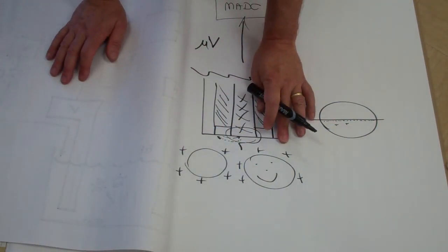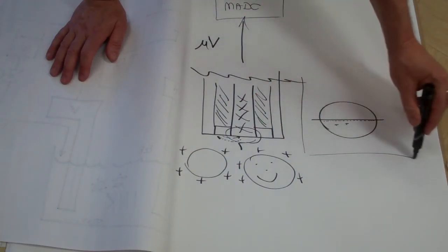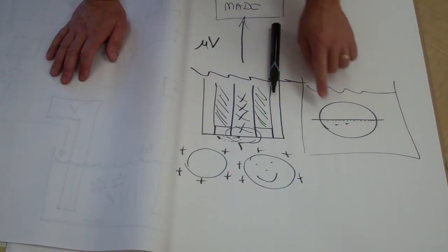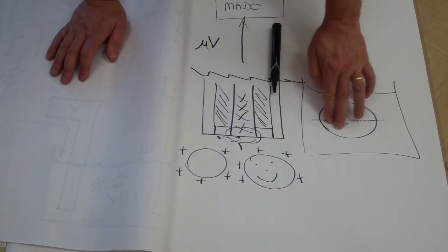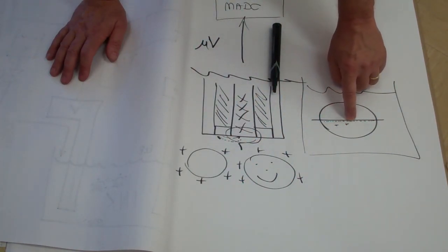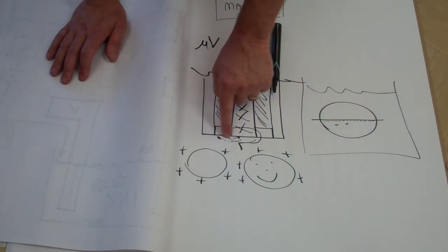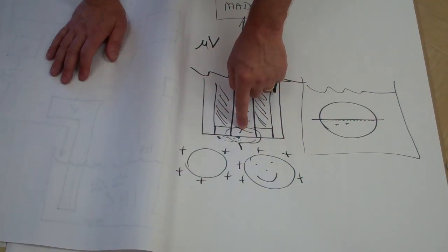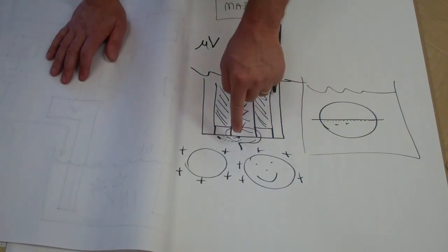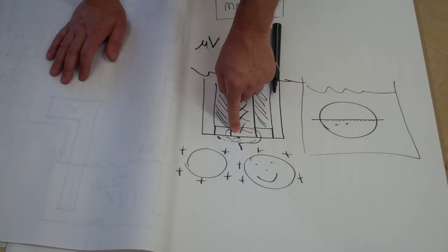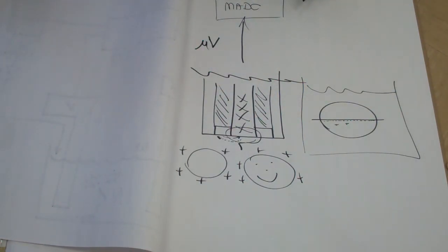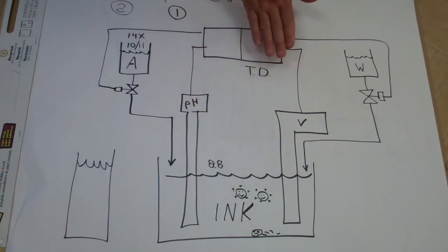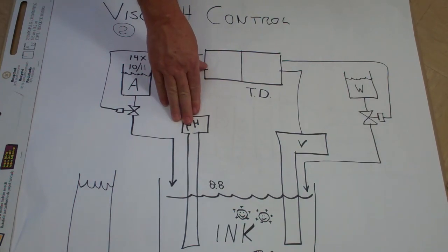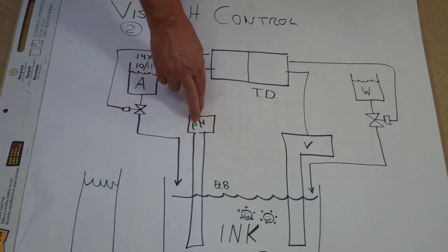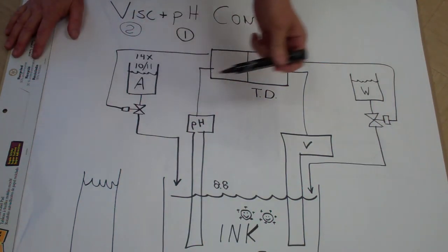And if you're taking a probe out and there's wet ink on it, the best thing is to put it into a cleaning solution, because if you take a napkin or a cloth towel and you start wiping the end of this, you can damage that very thin layer. If it's coated up and dried, take a screwdriver, you can break the glass. Keep them wet, keep them soaked. When they get dirty, there are cleaning solutions available, and you'll have success with pH control. Viscosity control is old hat. This is new to those who don't know about it, and these often need calibration to match the sensor.